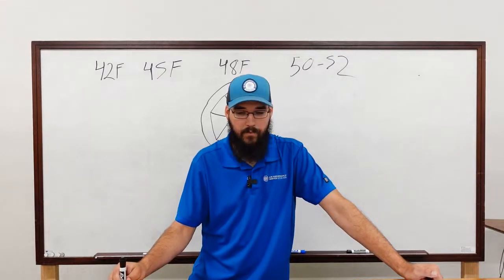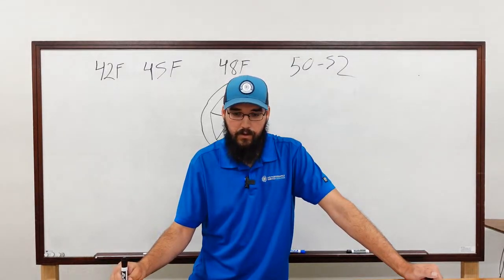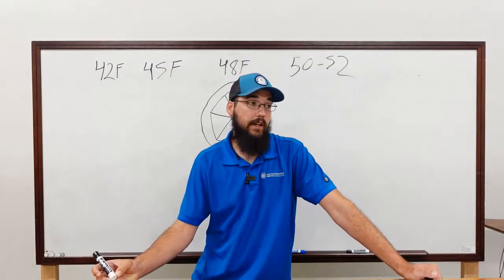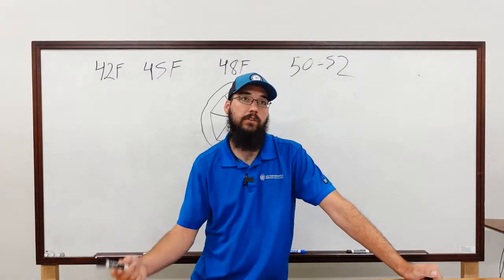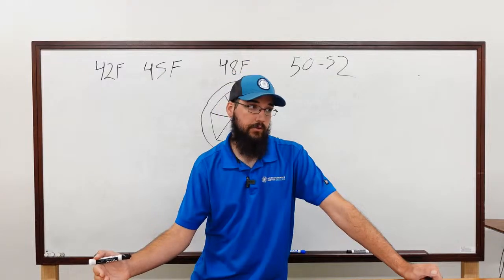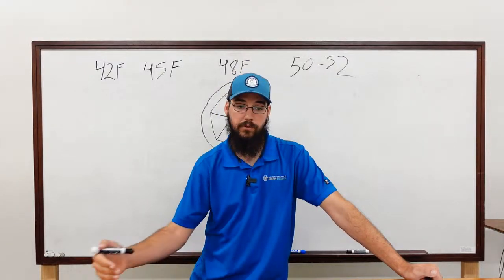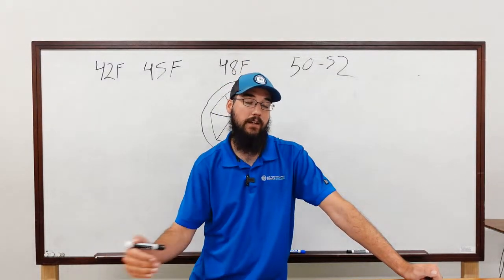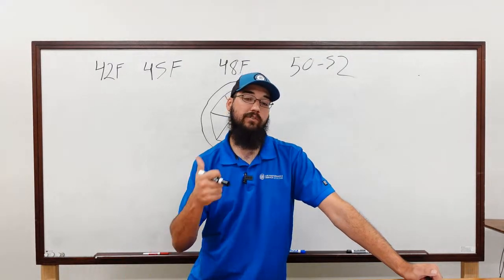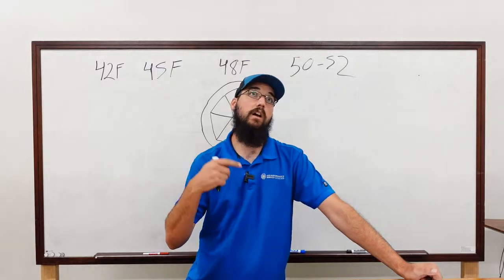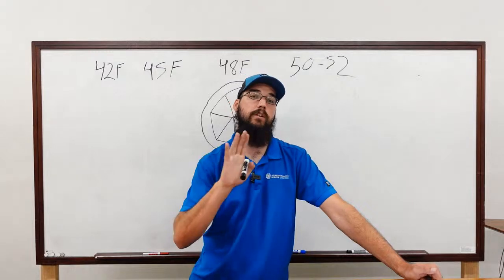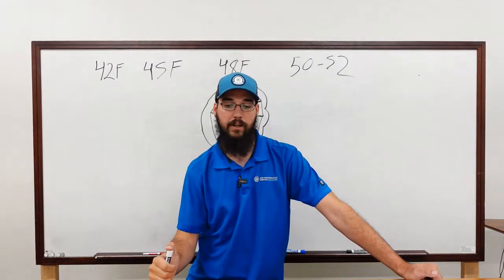Right. What about oilless compressors on low load conditions? Oilless, actually, that's one of the major benefits they have, because probably the most detrimental factor to oiled machines is the load conditions. You have to keep the lift and velocity at set minimums and the temperatures so that the oil viscosity, as well as the refrigerant velocity, is able to properly move and return the oil where it needs to go without it collecting in the wrong place.